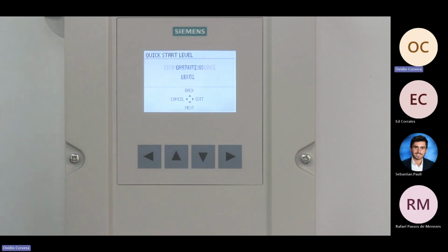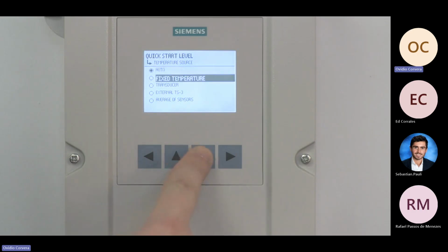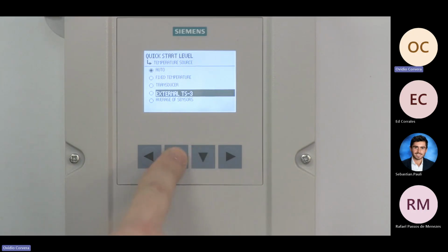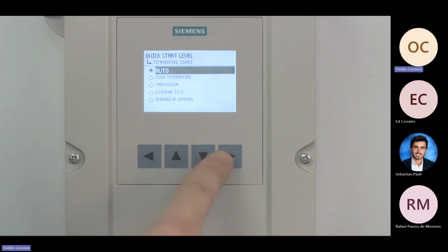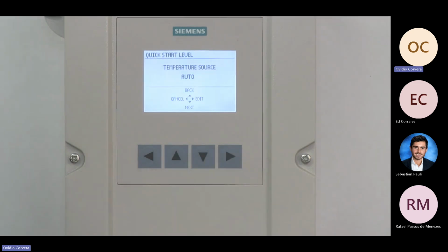Now let's select your temperature source. Press the right arrow to select Edit to change the temperature source. As the speed of sound changes with temperature, it's critical that we know the ambient temperature in the process to achieve an accurate measurement. The default temperature source is Auto. Using the up-down arrows, highlight your temperature source. If temperature changes quickly in your application, please use the TS3. It has a faster response than the transducer internal temperature sensor. Press the right arrow to enter your selection. Press the down arrow to select Next to proceed.